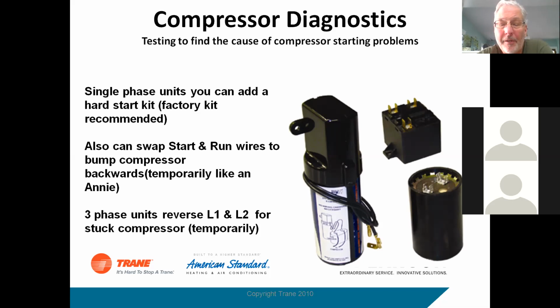Now on a three-phase unit, if you got a stuck compressor, you can try reversing L1 and L2, momentarily bump it and see if you can break the compressor free. They'll spin it backwards. Sometimes if you do that, you can break them free, reverse the wires, and the thing will run again. Although it may fail down the road. If it's been stuck, it's stuck for a reason. But there is a way to do that to try to get things running, to see if the system will work.